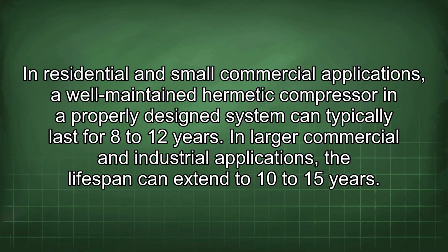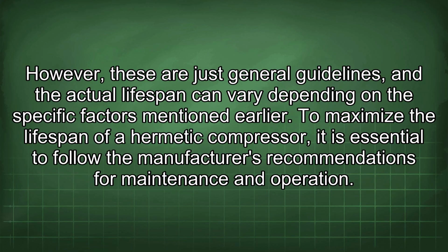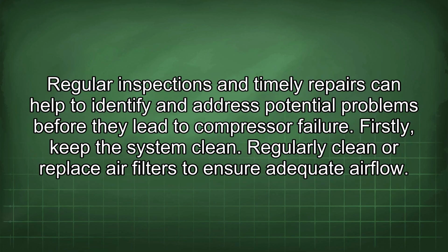In residential and small commercial applications, a well-maintained hermetic compressor in a properly designed system can typically last for 8 to 12 years. In larger commercial and industrial applications, the lifespan can extend to 10 to 15 years. However, these are just general guidelines, and the actual lifespan can vary depending on the specific factors mentioned earlier. To maximize the lifespan of a hermetic compressor, it is essential to follow the manufacturer's recommendations for maintenance and operation. Regular inspections and timely repairs can help to identify and address potential problems before they lead to compressor failure.